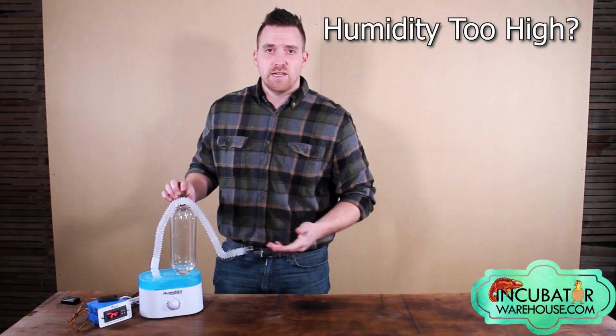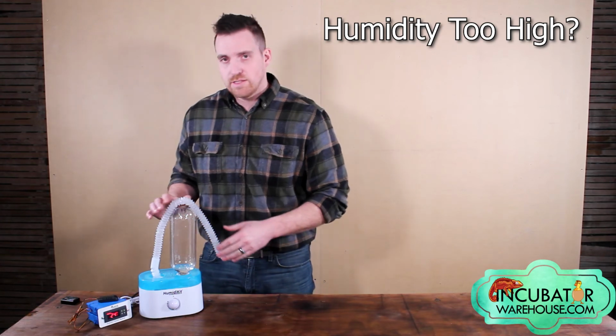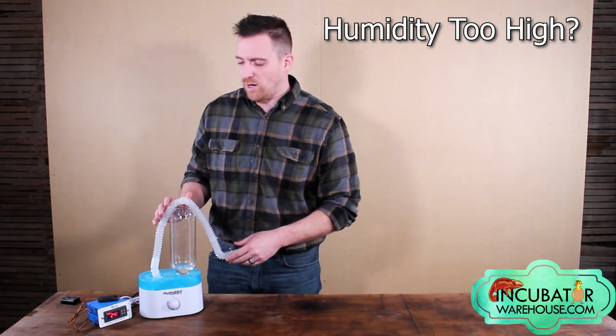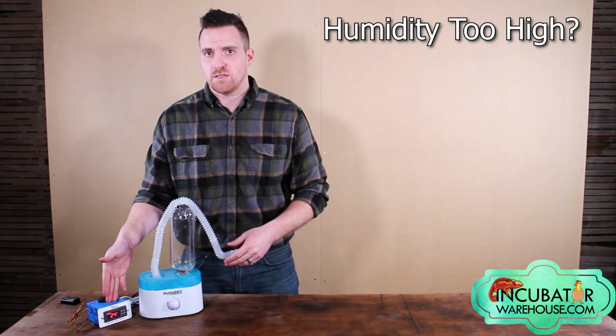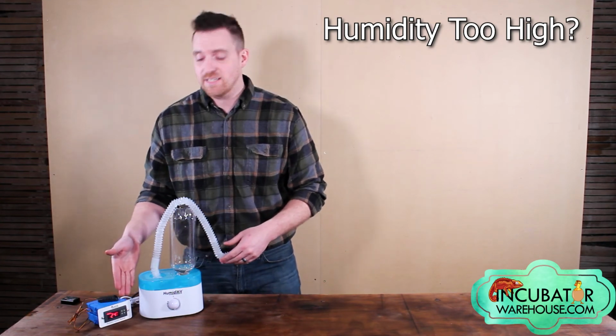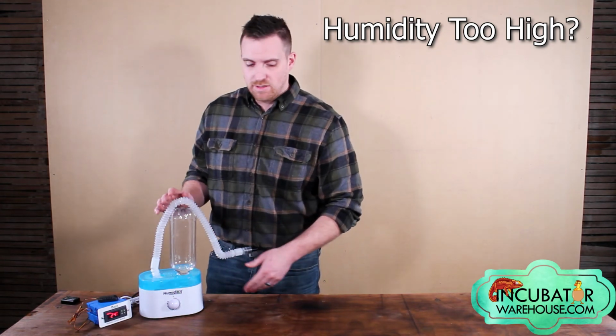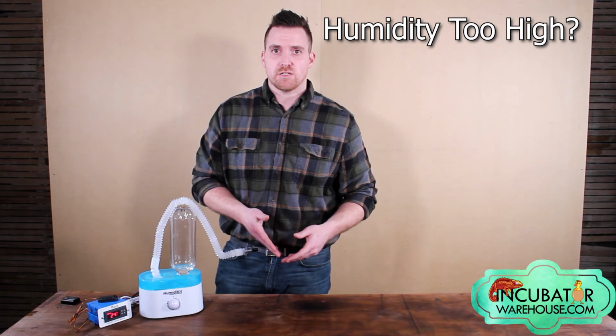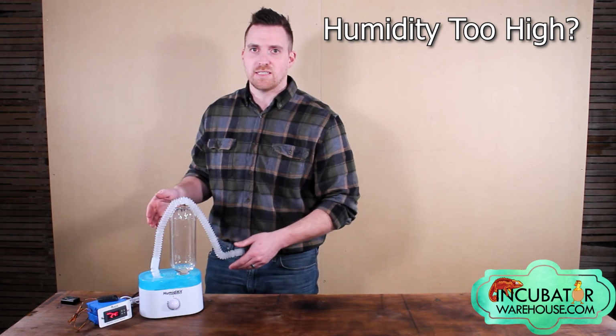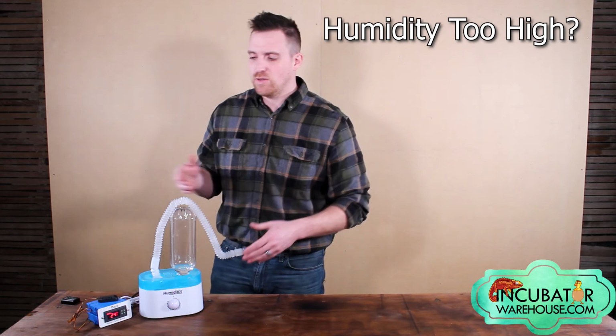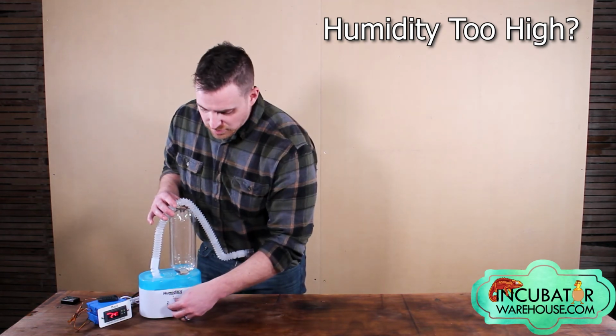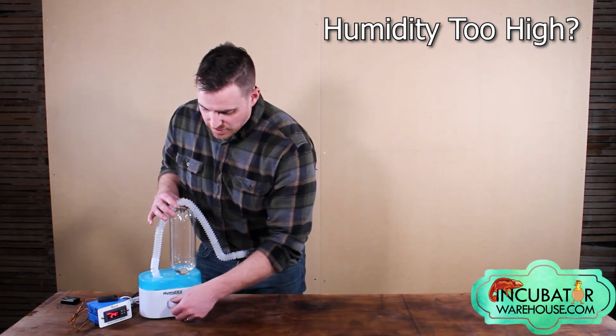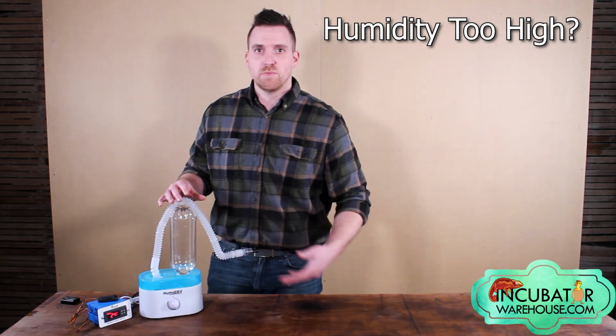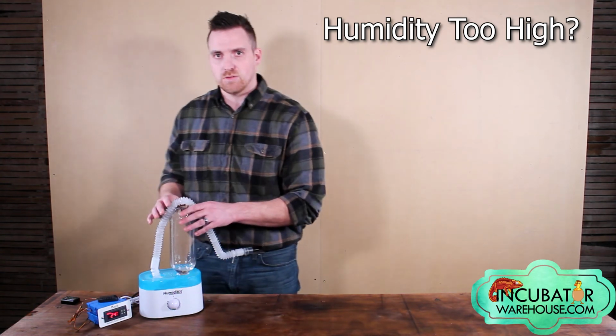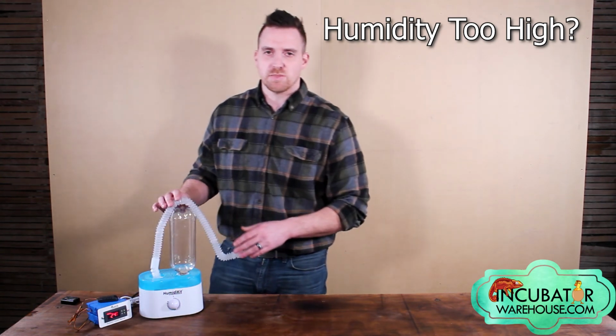One other problem you might encounter is your humidity level in your incubator is higher than you want it to be. There's a couple of things you should check to make sure things are working properly. Make sure your set point is set to the percentage that you want the humidity to be at and not higher than you were anticipating. Also, if you have used the humidity trays inside the incubator with the Humidikit together, it might be producing more humidity than you anticipated. You can adjust the amount of humidity produced by the Humidikit with the turn dial, or you can also remove the water from the tray inside the incubator and only use the Humidikit to make sure you stay as accurate as possible.